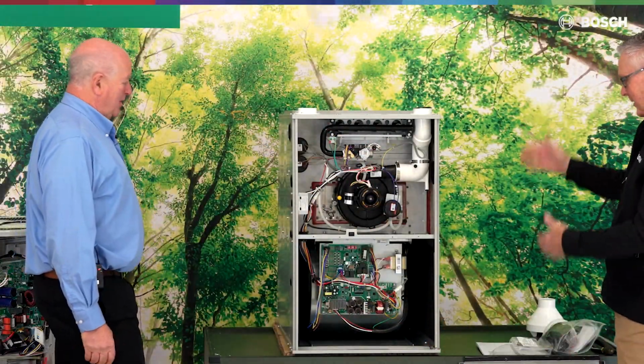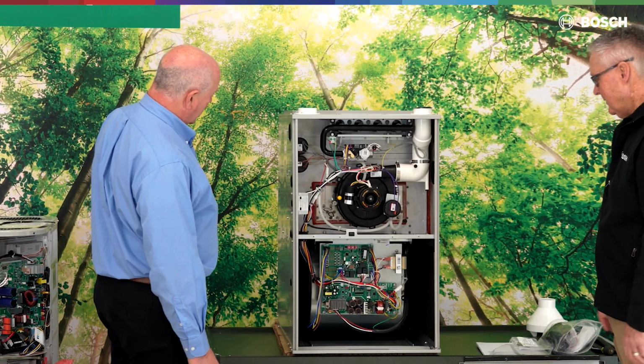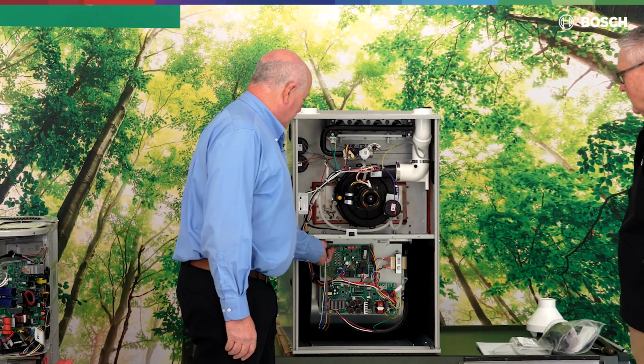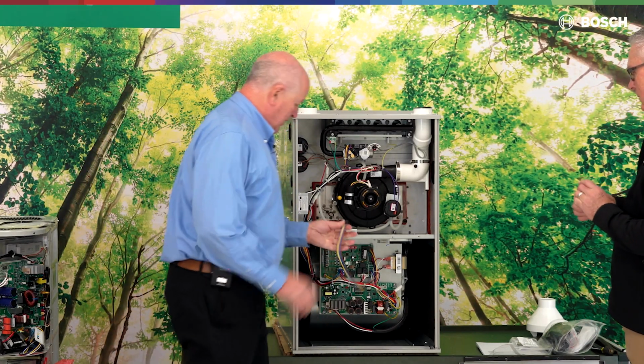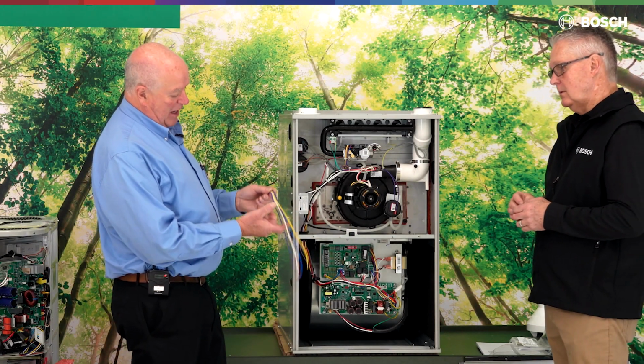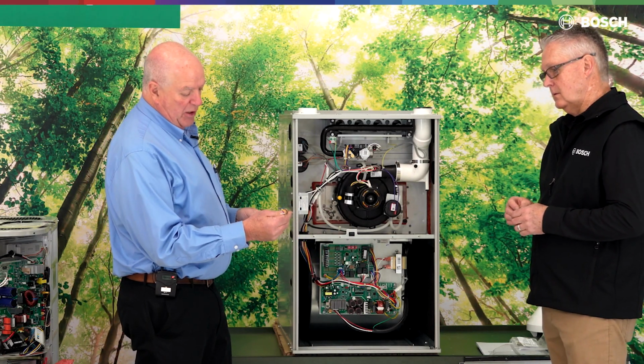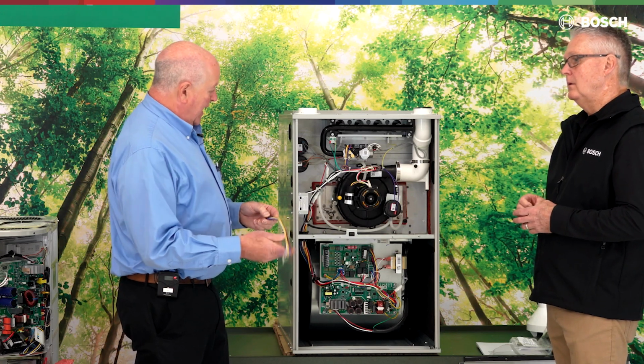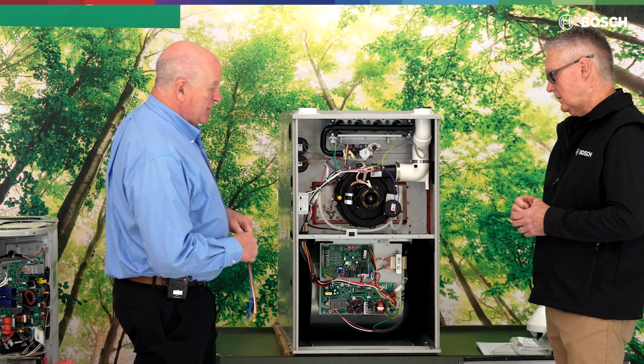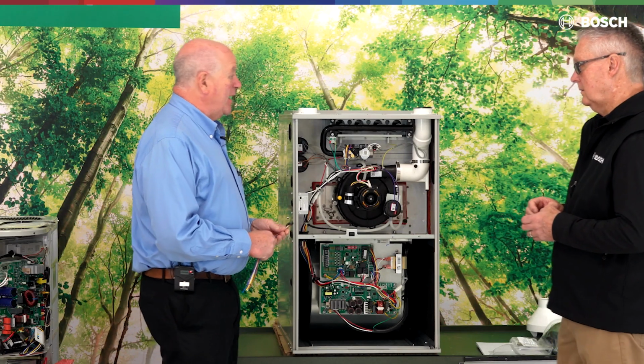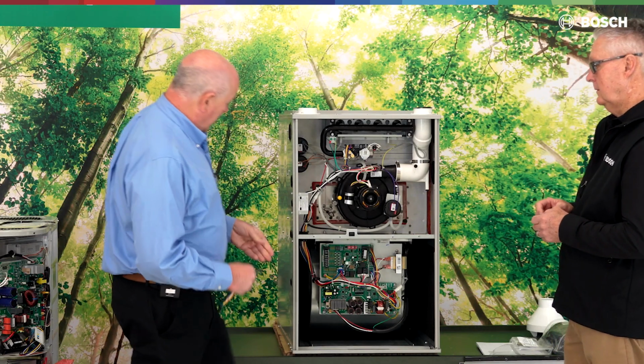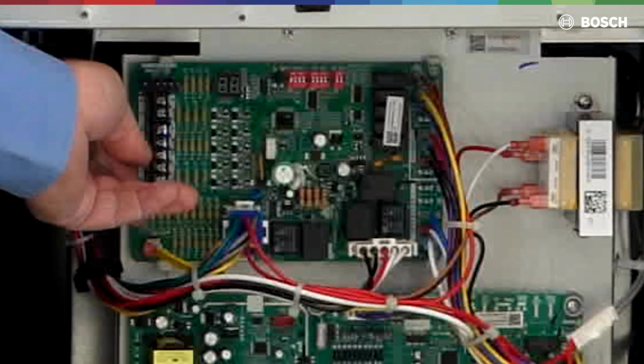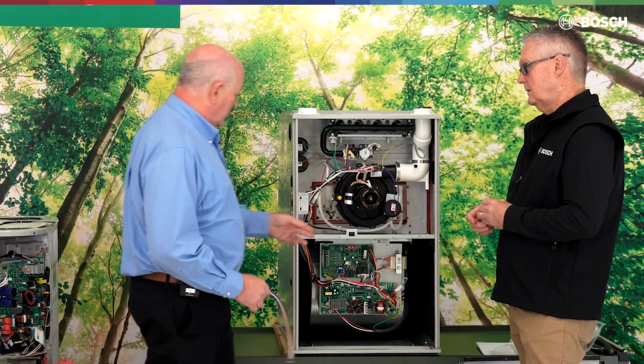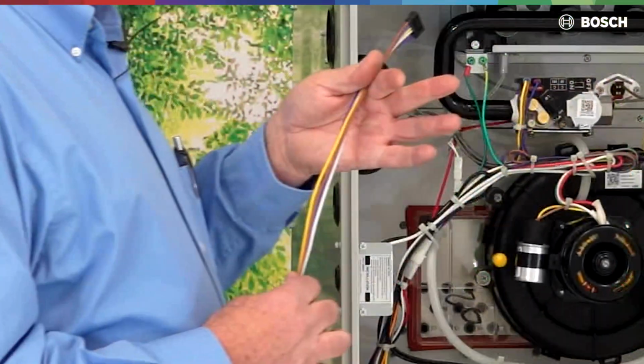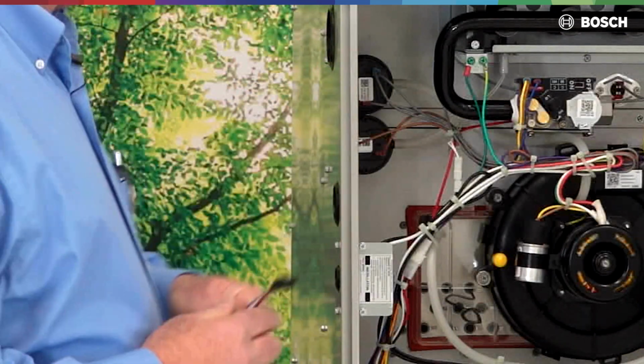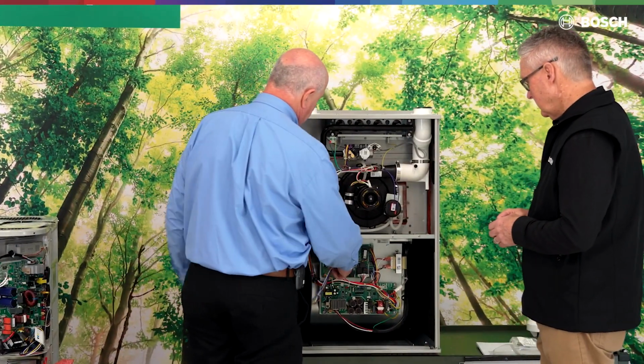There's a couple things we want to bring attention to here. There was a new sensor wire or cable that came with the unit. We said it was a thermostat wire, but actually it's for the outdoor unit of a Bosch IDS, used with the A2L sensor. If this is an older system that doesn't require A2L, using R410A, we can make those connections right here on the board. But if it's an A2L sensor setup, where the A2L shuts off the outdoor unit, we have to use this plug connector instead, which comes out through the grommet on the side.